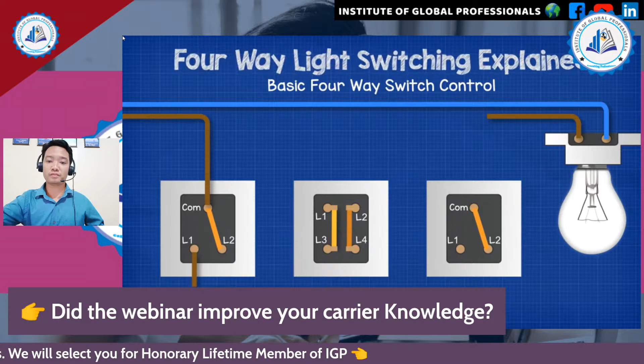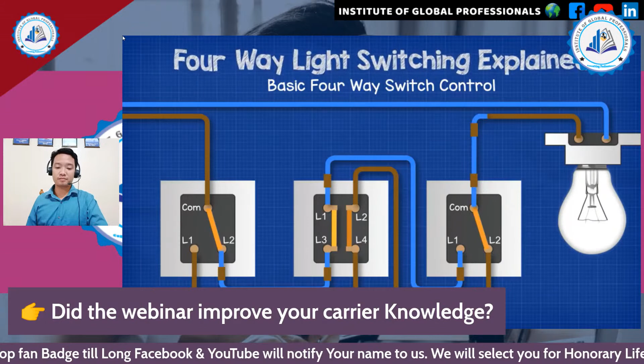We take the live and feed it into the common of switch 1. We run a brown cable from L1 of switch 1 to L4 of switch 2, then another brown cable from L2 of switch 2 to L2 of switch 3. We run a blue wire from L2 of switch 1 to L3 of switch 2, placing a brown sleeve at each end to warn it is intermittently live. We run another blue wire from L1 of switch 2 to L1 of switch 3, and a final blue wire from the common of switch 3 up to the light.